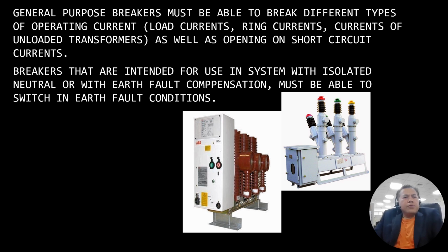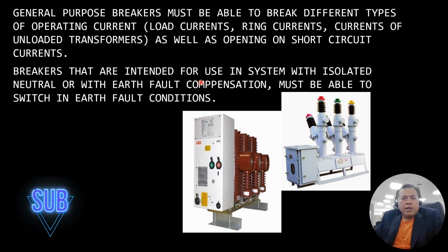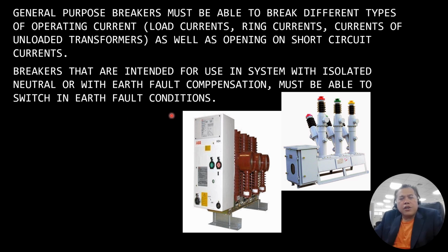So general purpose breakers must be able to break different types of operating current: load current, ring current, currents of unloaded transformers, as well as the opening of short circuit current. Breakers that are intended for use in systems with isolated neutral or with earth fault compensation must be able to switch in the earth fault condition.